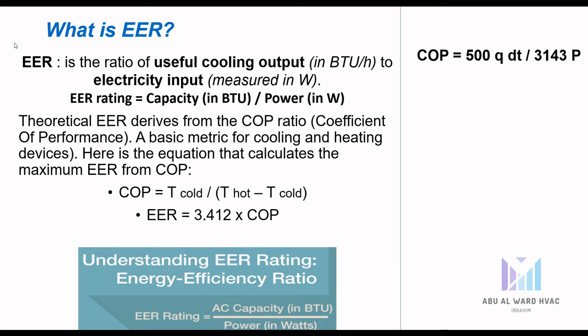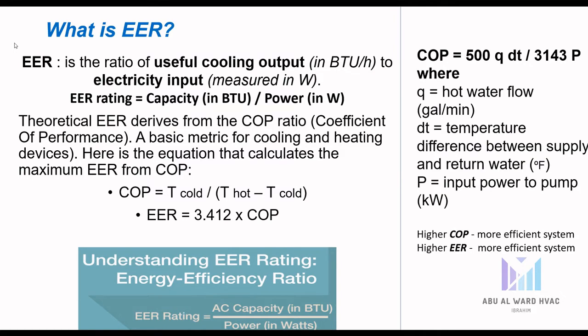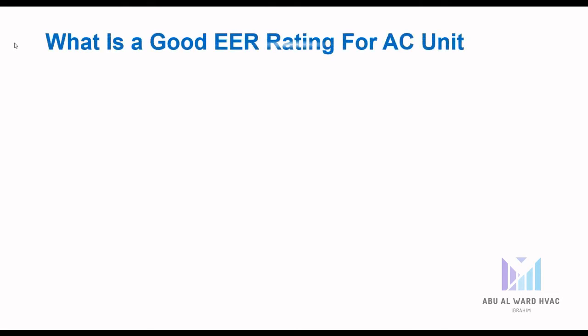COP also equals 500 × Q × ΔT divided by 3143 × P, where Q is hot water flow in gallons per minute, ΔT is the temperature difference between supply and return in Fahrenheit, and P is the input power to the pump in kilowatts. We also need to know that the higher the COP, the more efficient the system — the same applies to EER: higher EER means a more efficient system.